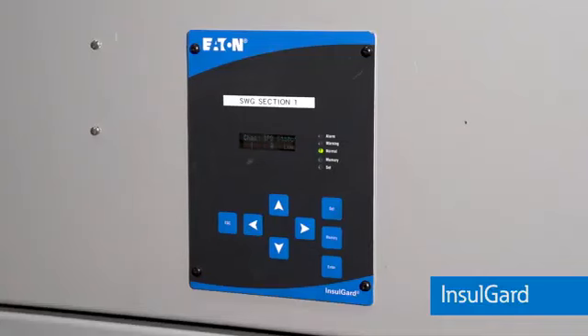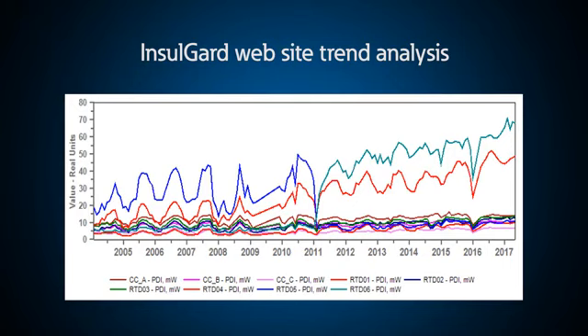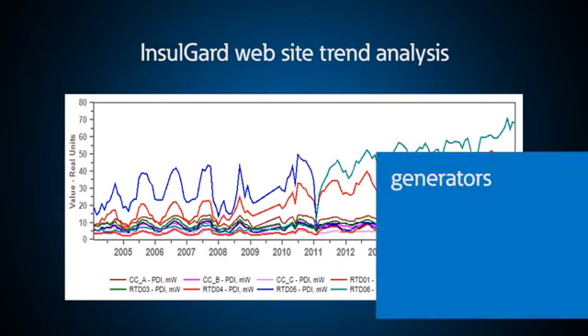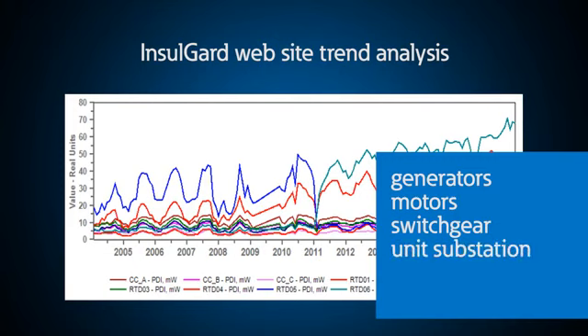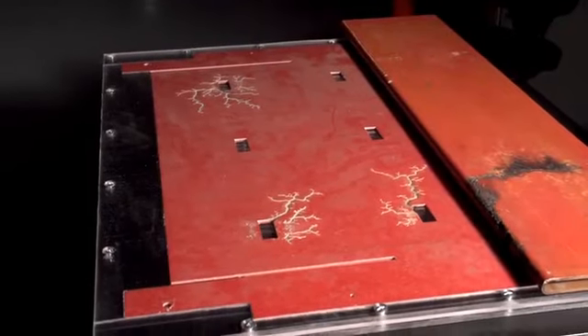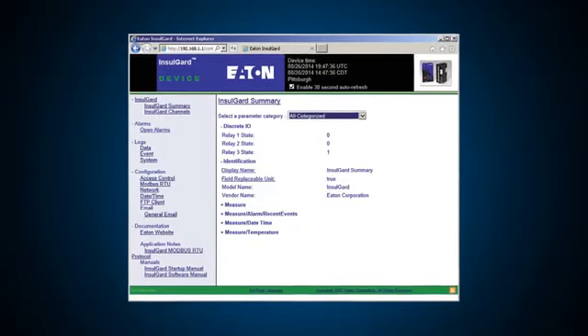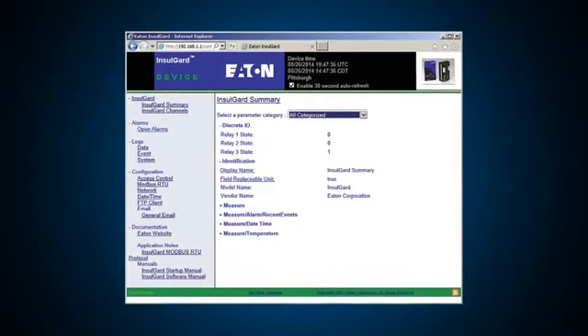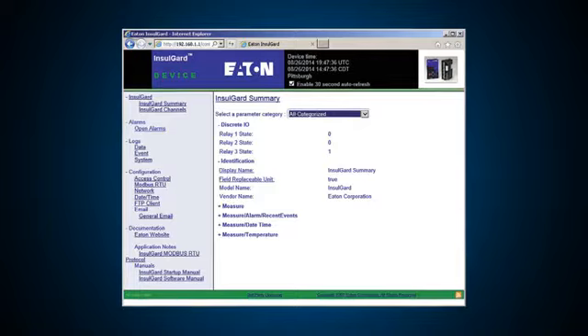InsulGard provides continuous, non-invasive online monitoring of medium voltage generators, motors, switchgear, unit substation dry type transformers, bus duct, and cable connections. The benefit is that you can prevent flashovers of insulation and potential arc flash conditions. With very inexpensive monitoring, you can get notifications before something happens and you can take steps to fix potential issues.